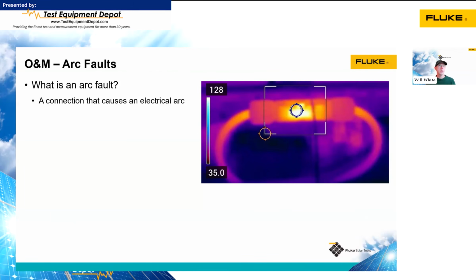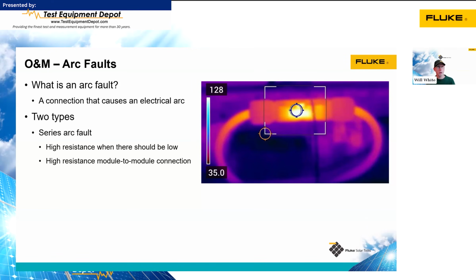Another problem we see with systems in operations and maintenance is arc faults. This is an arcing electrical connection, and there are 2 types of arc faults. Series arc faults are a high resistance connection where there should be a low resistance connection. And this picture on the screen is a good example here. This is a module to module connector where it either didn't get plugged in all the way or somebody made a bad field crimp and there's not a good connection there and it's arcing, and that arcing is causing some heat. Eventually that will continue to heat up and the arc will get longer and longer until it burns out like the connector we saw a couple slides back.